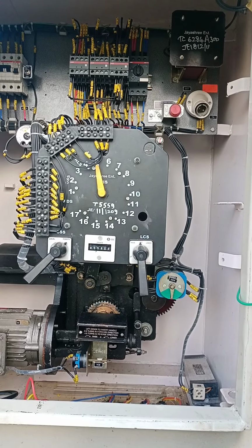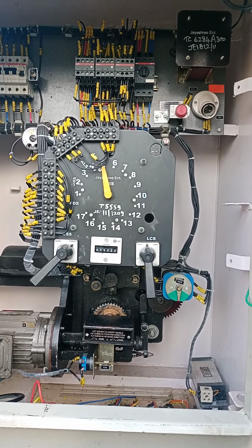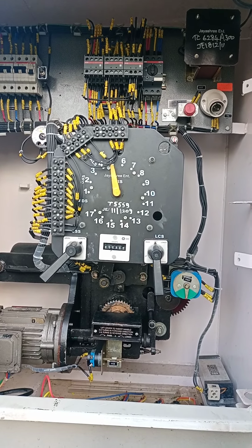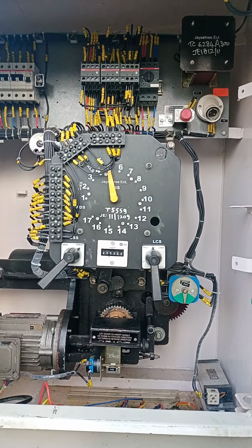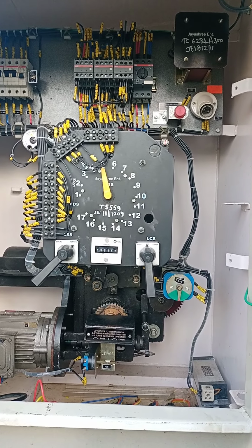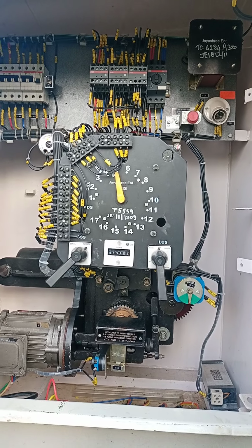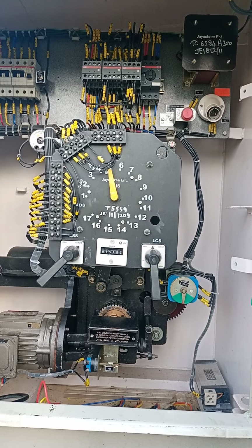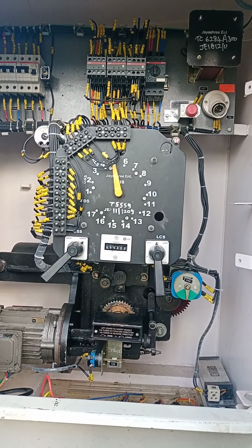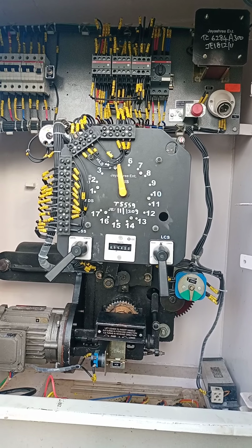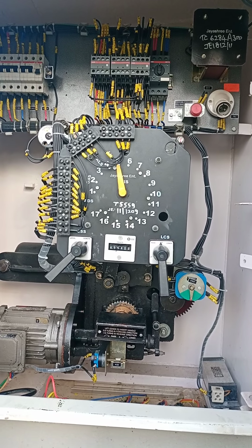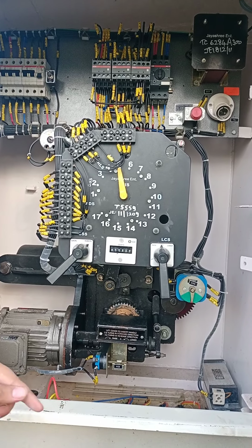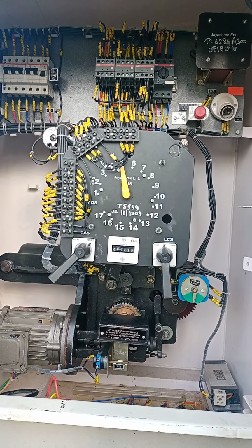How does it operate? First of all, the operation can be in two ways. One is through remote and another one is through local. For remote operation, you will select the selector switch there, and give the command. For example, if your voltage has decreased and you want your tap to increase, you will give the step up command through the push button. Your contactor will pick up and give the three phase supply to the motor. As the three phase supply goes to the motor, it will move through the gear one tap position up.